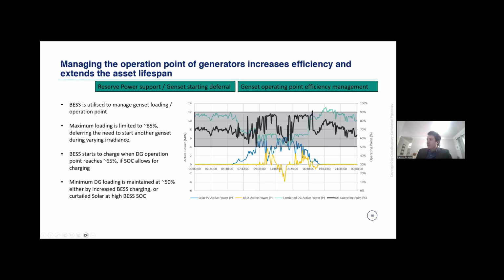And once solar PV generation increased again, we were able to decrease the amount of active power injected by the battery, allowing us to not start that genset. Because obviously you don't want to go starting gensets every couple hours. That's also not great for the lifespan of the gen, and you're increasing maintenance activity, etc., which doesn't bode well for an efficient system.